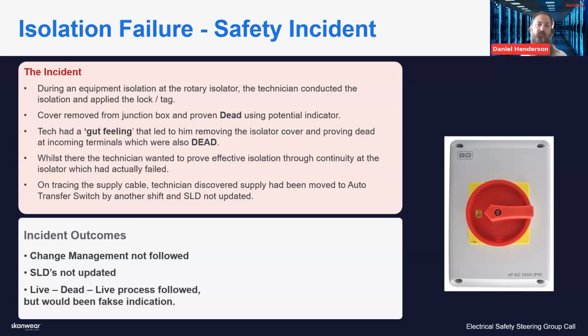The technician then removed the cover from the junction box, and using a potential indicator, did the live dead live process and proved dead at the point of work. There was no indication, and the test instruments worked, so all good.